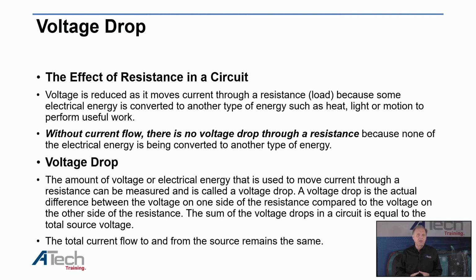We do know that occasionally we're going to have connection problems on circuits because they're not feeding together correctly, like this if I do the circuit. So you need to look at a circuit and compare it, going down the line, always doing the voltage drop to see where you're losing voltage before your load.